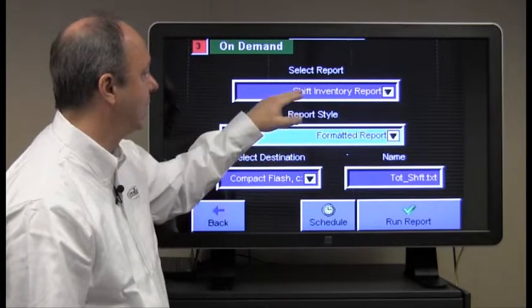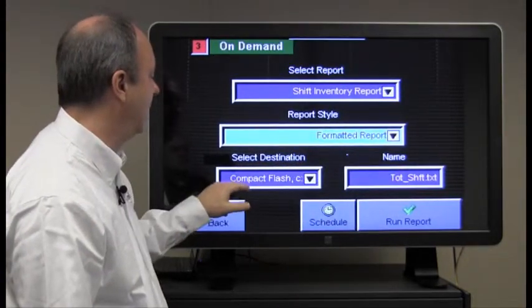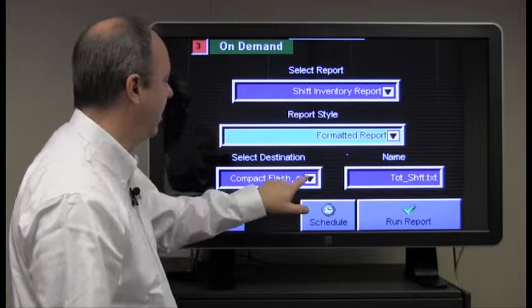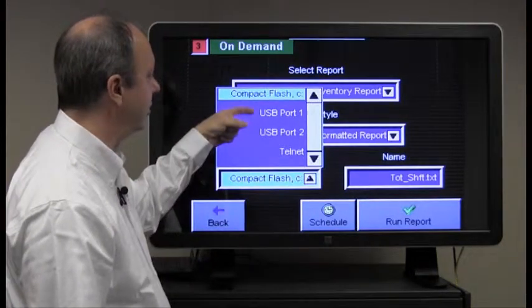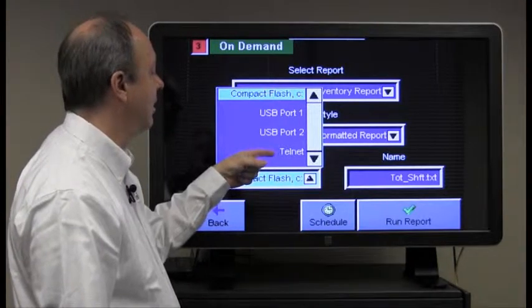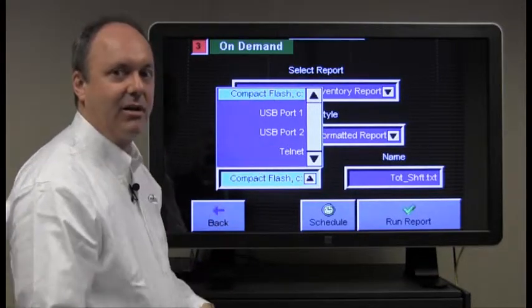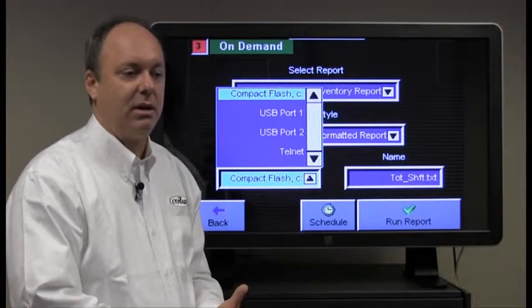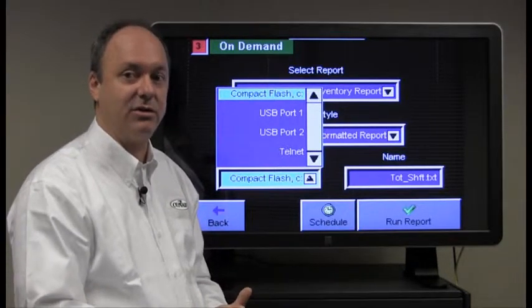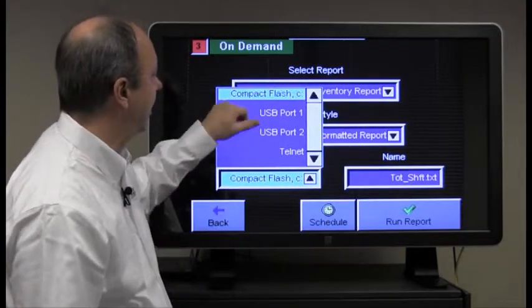The destination is where you'd like the inventory report in a formatted format to go. So in this particular default, it is the compact flash card that's located in the top of the TrueBlend SB2 touch screen. The other choices there are the USB ports, one and two, located on the touch screen beneath the touch screen. As well as an Ethernet connection with a protocol called Telnet. Telnet is an industrial trademark name that is a common protocol used with hyperterminal, other software programs, freeware such as TerraTerm. These are both software packages that allow you to establish a Telnet connection, which is the protocol, back to the touch screen. So we'll select compact flash in this case.